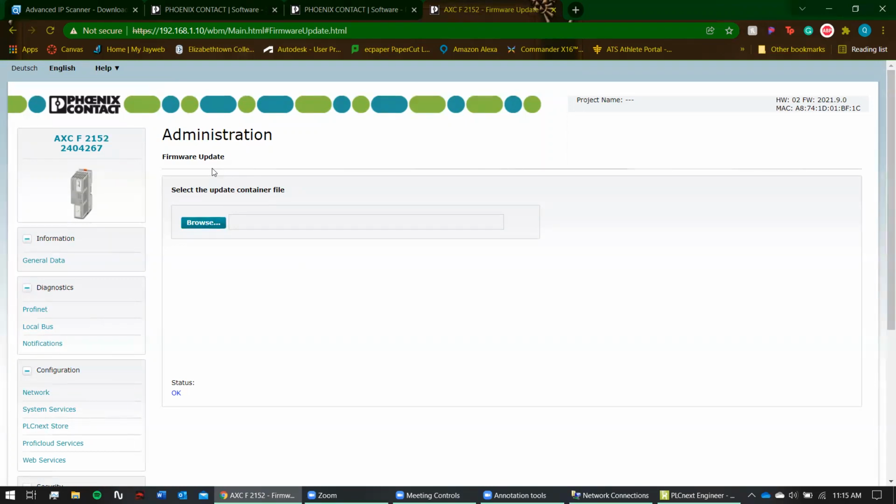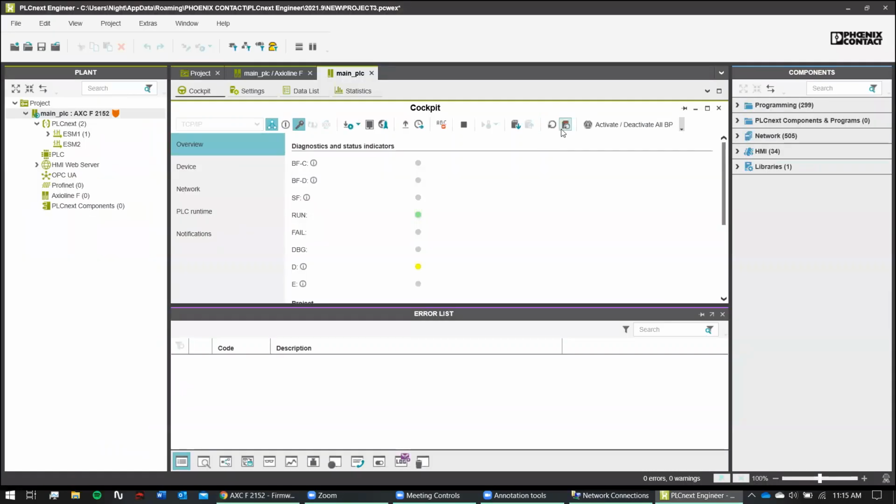Now, if you have a controller and this web service management was disabled on it, it's going to make it a little bit of a pain. So I would recommend resetting the controller through the PLCnext software. If I connect here, you can go to this button here and it resets the controller to factory defaults. Then from there, you'd be able to reconnect to the web service management, do those couple configuration things there, and update your firmware. The firmware determines which version of your software you can use. So the more you update your firmware, the better the software you have at your disposal.